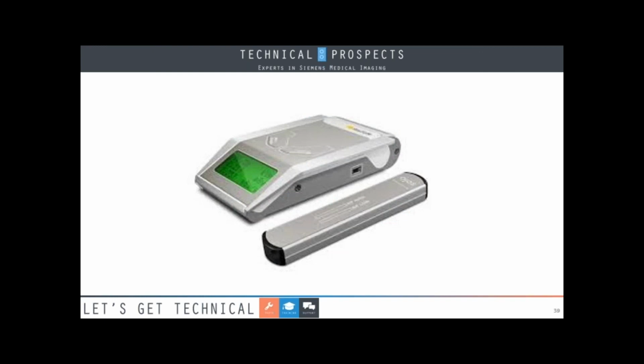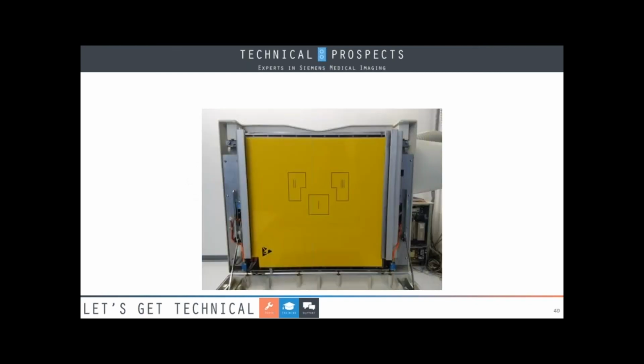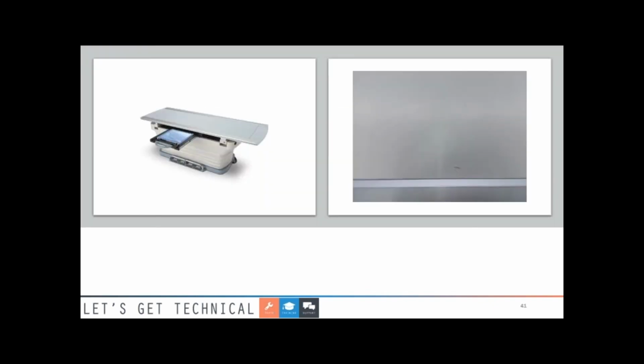After that, what's your KV or MA? The doses for KERMA, KV, and MA should be checked during certain preventive maintenance cycles, usually every 2 years. If the doses are good, but maybe we have what's called an automatic exposure control, okay? Operators have the luxury of not having to do anything. They can just pull up and say, okay, I'm going to do a skull. This is the patient's weight. This is their gender. This is everything. And then it decides what to do because you have this nice little chamber back there. And basically, that's like film. It's choosing the speed film. So if one of those isn't working, they're not going to be able to do it automatically. And they're going to have to figure out how much time or KV or mAs to use. So if that happens, you're going to want to look at that guy.